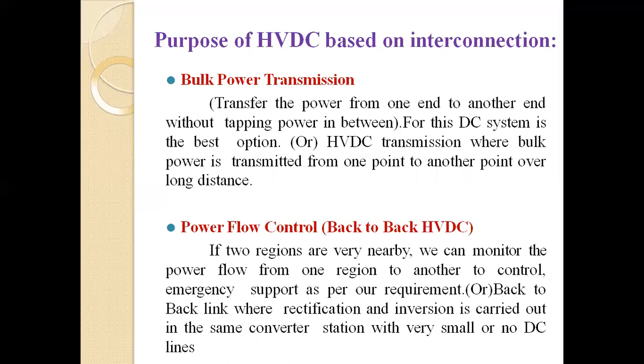Second is power flow control, which means the back-to-back HVDC system. If two regions are very nearby, we can monitor the power flow from one region to another to provide emergency support as per our requirement, using a back-to-back link where rectification and then inversion are carried out in the same converter station with a very small or no DC line. So if the two regions are very near, we can control the power.